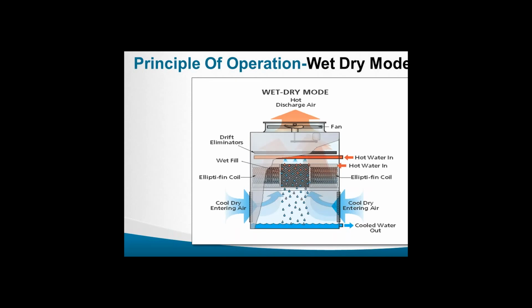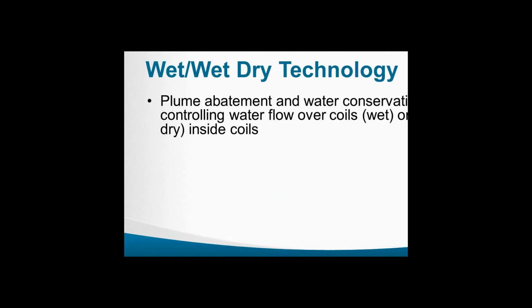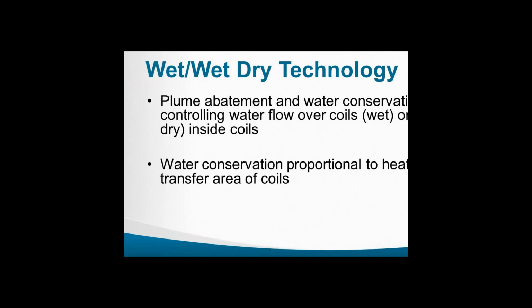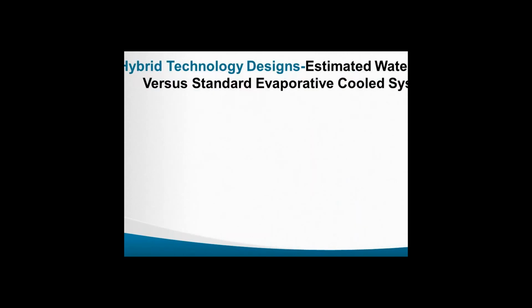Now, in the wet-dry mode, you just direct that water over the fill pack, and then these run dry, but some of the load is put through these Ellipti-fin coils, stainless steel coils. So you get your water savings with that kind of design. You also get some plume abatement with that. And the more coils you put in that design, the more water conservation you'll get. And they estimate 20 to 30%.